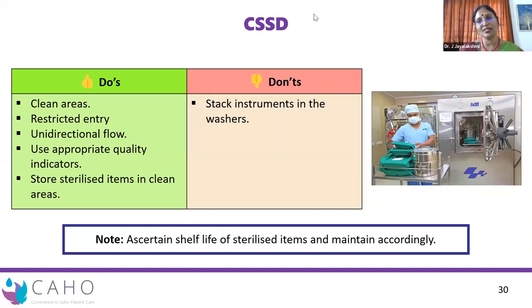Whenever you're using an implant, certain hospitals would have implants. Sterilization of implants should never be done in a flash sterilizer. And any batch that has an implant being sterilized, that batch, even if you've done one the previous day, you need to put a biological indicator in the batch in which you will have your implants being sterilized. So these are very, very simple things, but you need to follow them very carefully.